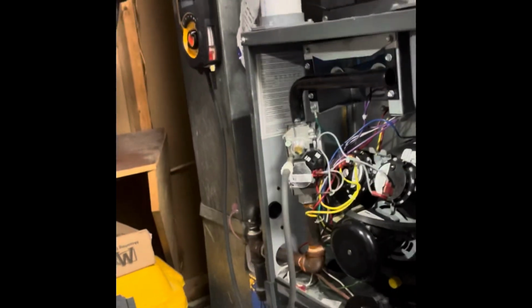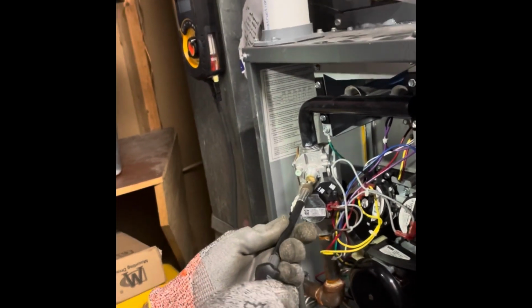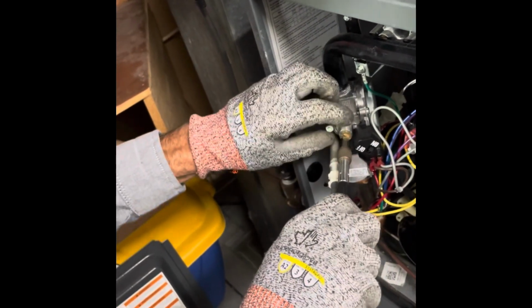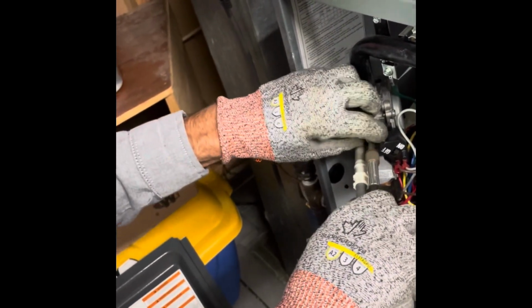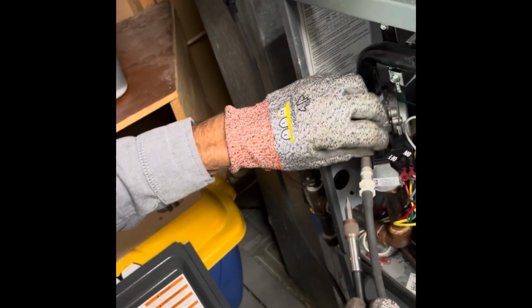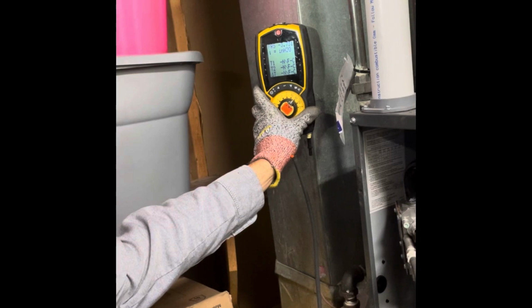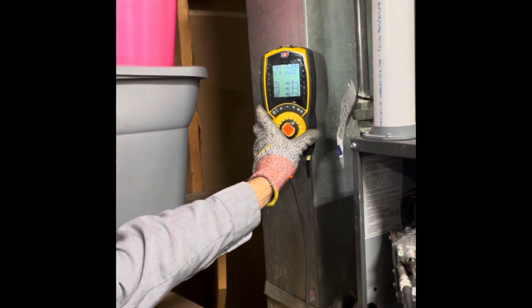So with these, I find the easiest way to try to get this screw out without wrecking it, I'm going to tighten it first, just a little hair. So I felt it move, now it'll back off. So that way I can get that screw out without stripping it. If I were to just turn it to the left, it would have taken a chunk of brass out and this cap would have been in place till we got a new valve put in. So to adjust our gas pressure, I'm going to go counterclockwise. So if you look, our number's slowly going down.